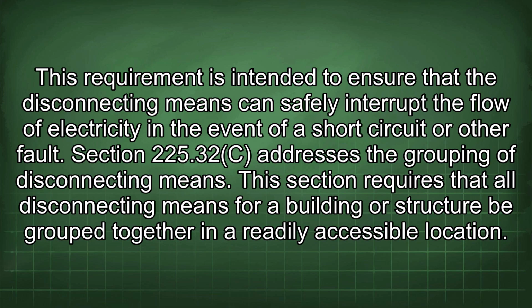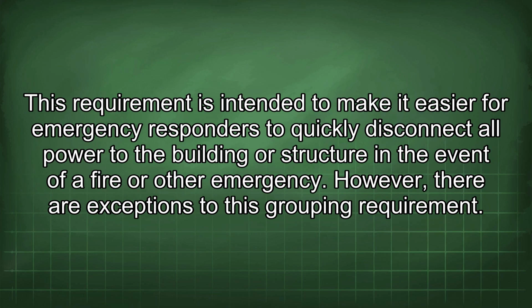Section 225.32c addresses the grouping of disconnecting means. This section requires that all disconnecting means for a building or structure be grouped together in a readily accessible location. This requirement is intended to make it easier for emergency responders to quickly disconnect all power to the building or structure in the event of a fire or other emergency. However, there are exceptions to this grouping requirement.